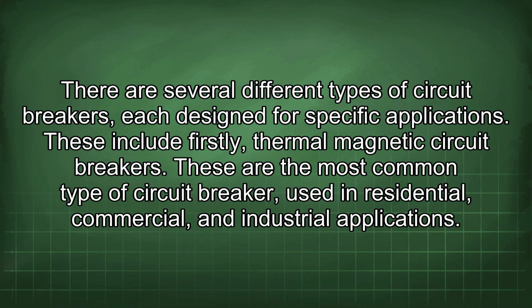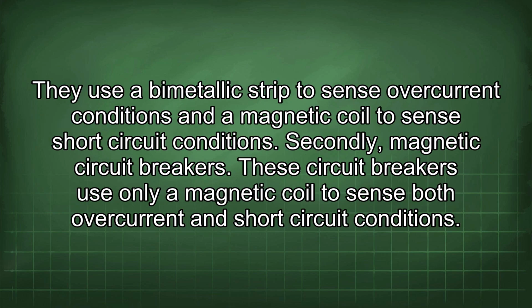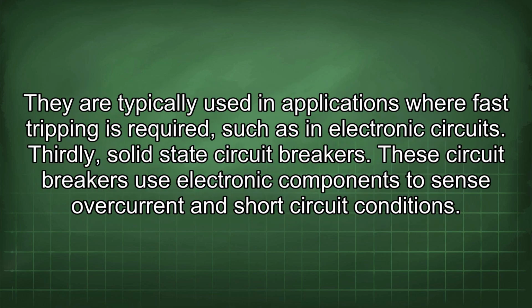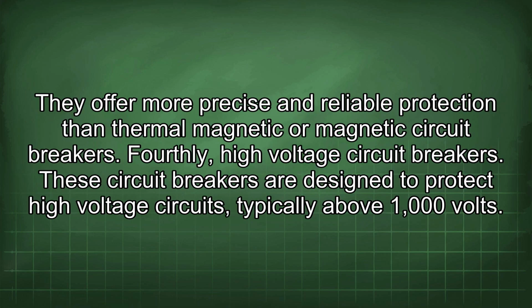These include, firstly, thermal-magnetic circuit breakers. These are the most common type of circuit breaker used in residential, commercial, and industrial applications. They use a bimetallic strip to sense overcurrent conditions and a magnetic coil to sense short circuit conditions. Secondly, magnetic circuit breakers. These circuit breakers use only a magnetic coil to sense both overcurrent and short circuit conditions. They are typically used in applications where fast tripping is required, such as in electronic circuits. Thirdly, solid-state circuit breakers. These circuit breakers use electronic components to sense overcurrent and short circuit conditions. They offer more precise and reliable protection than thermal magnetic or magnetic circuit breakers.